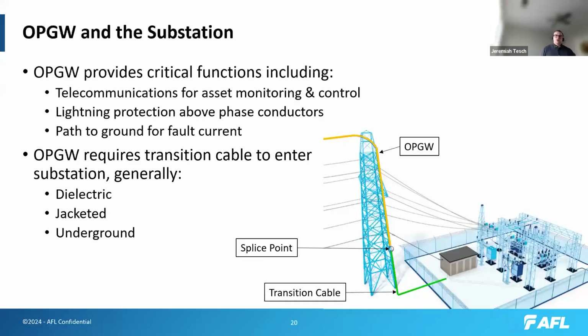All right, and just to touch back on how OPGW relates to the substation. Like I mentioned, this is providing lightning protection, the path to ground for fault current, and also your telecommunications. Primarily in the utility or the transmission line space, this will be providing telecommunications for asset monitoring and control, monitoring your substation and other assets along the power grid. But we do see some utility companies leasing out fiber to third parties, though a lot of them have restrictions on the ability to make profits and things like that. So definitely understand that. But those are some of the use cases. Primarily, the optical ground wire is used for just asset monitoring and control.